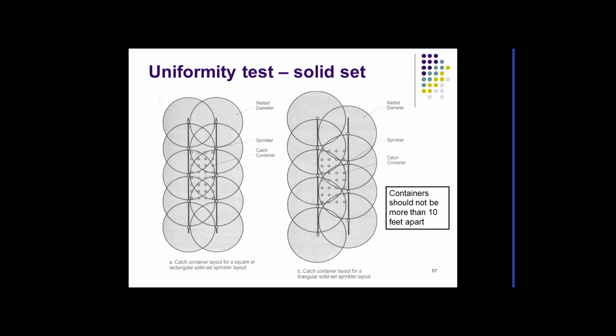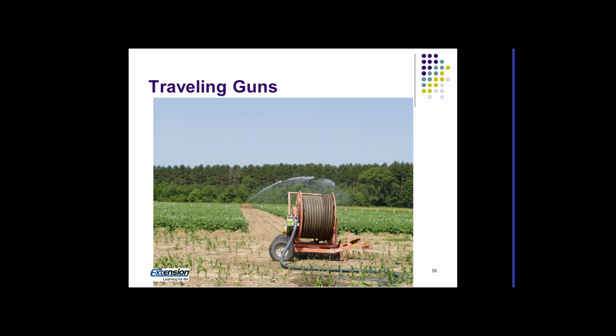We can also do this test on a solid set or movable system, and here we would just set the cups out between the sprinklers. We'd set a grid pattern. Now we can't do the whole system here, we can only spot check it. So we'd set it out. Typically we'd recommend they be no more than 10 feet apart. We'd set that pattern up and catch the water and calculate the number as basically an average number. But it can be done in this case as well as on traveling guns.